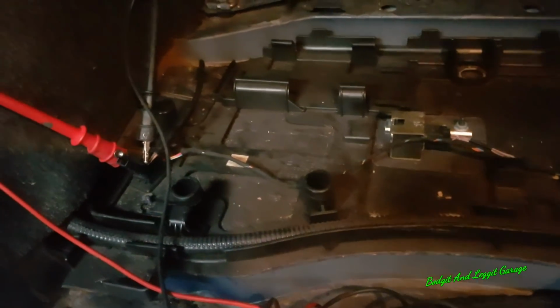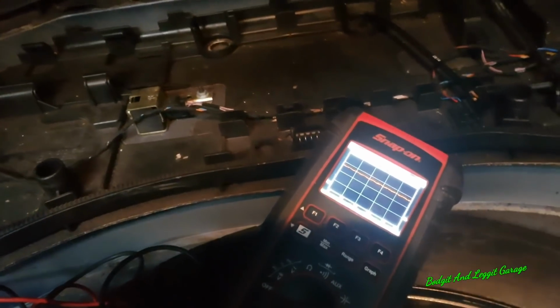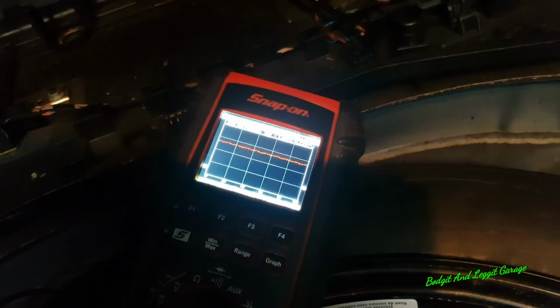Right, so absolutely nothing coming from that sensor. Now what does that tell us? Does that tell us we've got an issue with the sensor? Well, no. Does that tell us we've possibly got an issue with the sensor? Yes. We know the wiring is good because we've kind of done the load test, so that suggests - again, not 100%, but for the test we're doing, it's quick and easy.